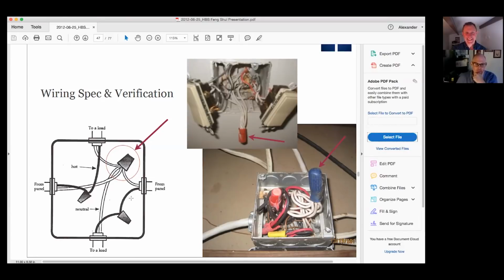Every time, if we include in the specification to return when the electrician thinks they're done, we do some verification testing back at the electrical panel, and sure enough, neutrals from these two circuits are touching somewhere out there. They have to go dig around and find things like this. It can take a lot of time and be challenging and expensive to fix later. It's a code violation that doesn't negatively impact how the lights work, how the dishwasher runs. Everything still works as it should.